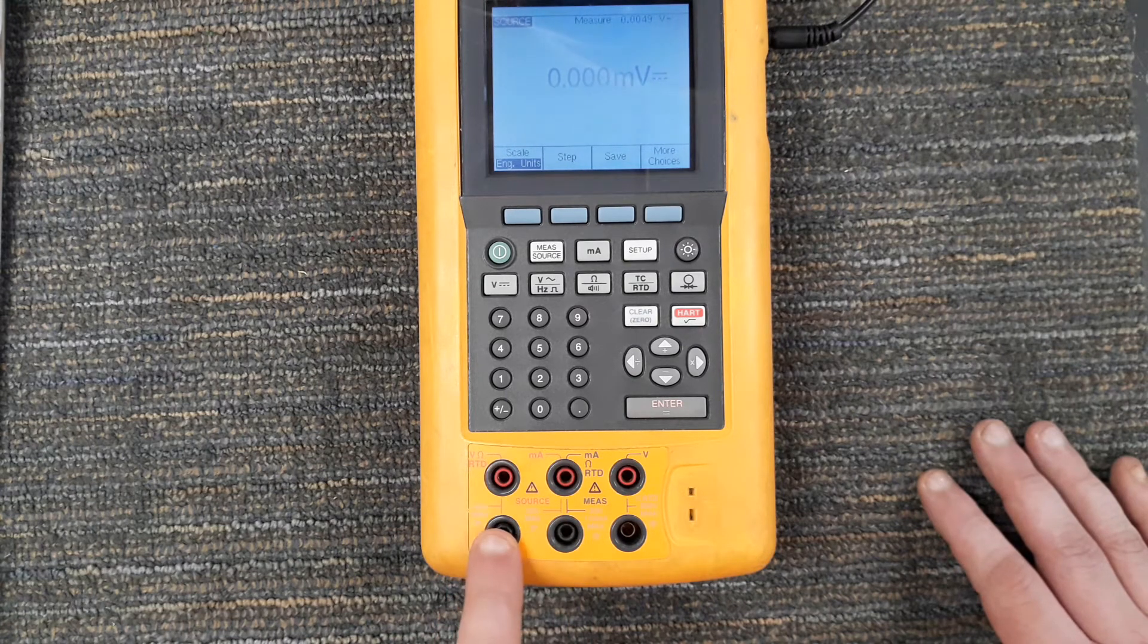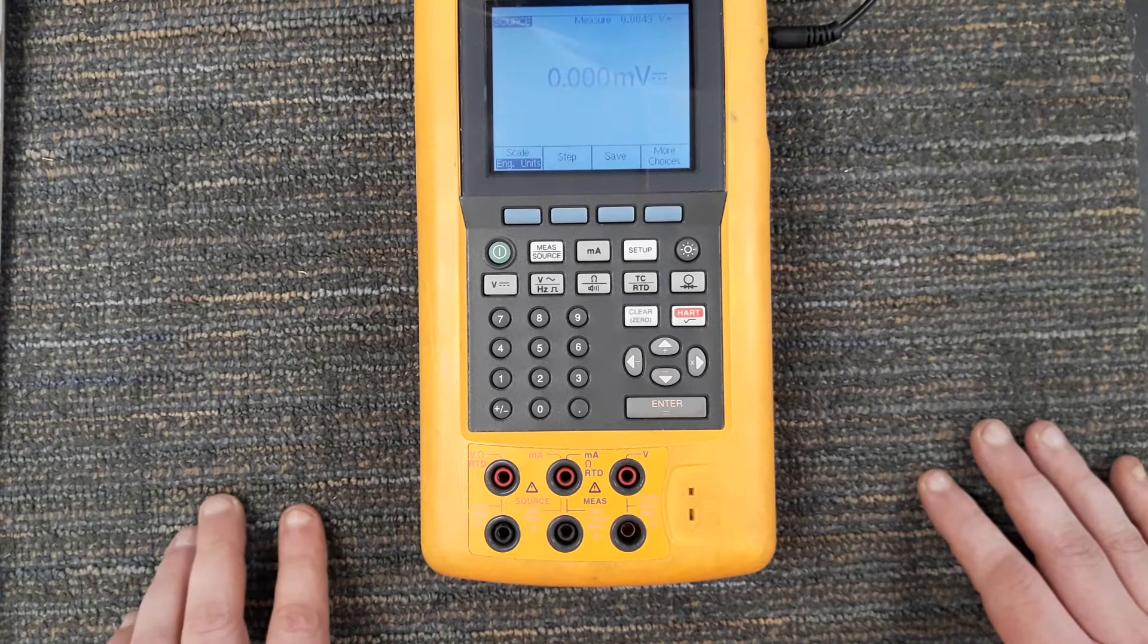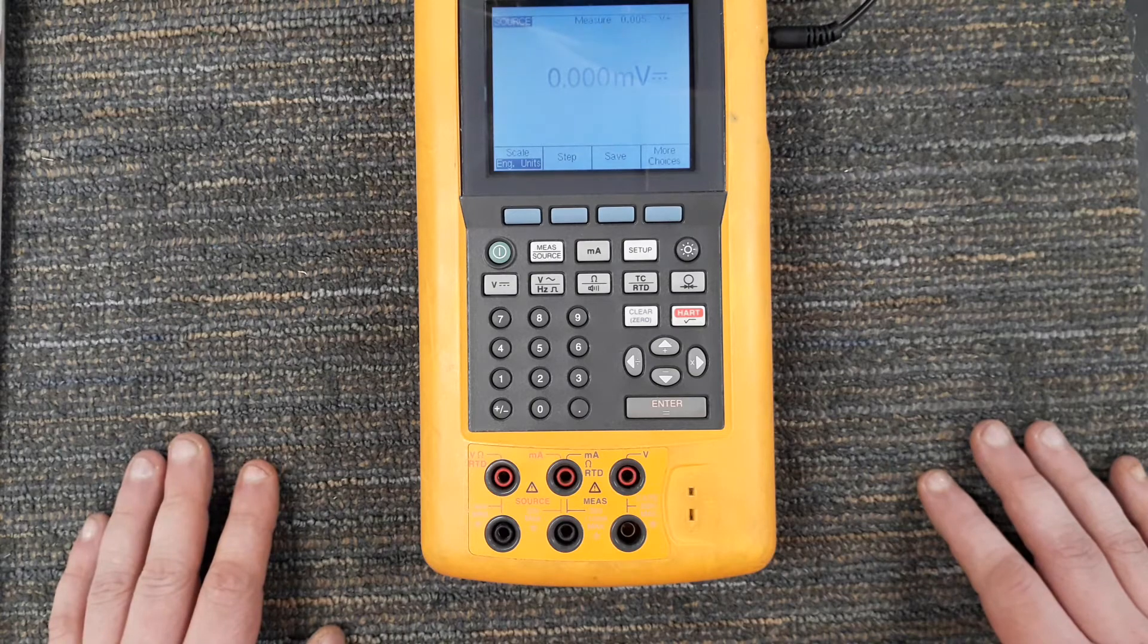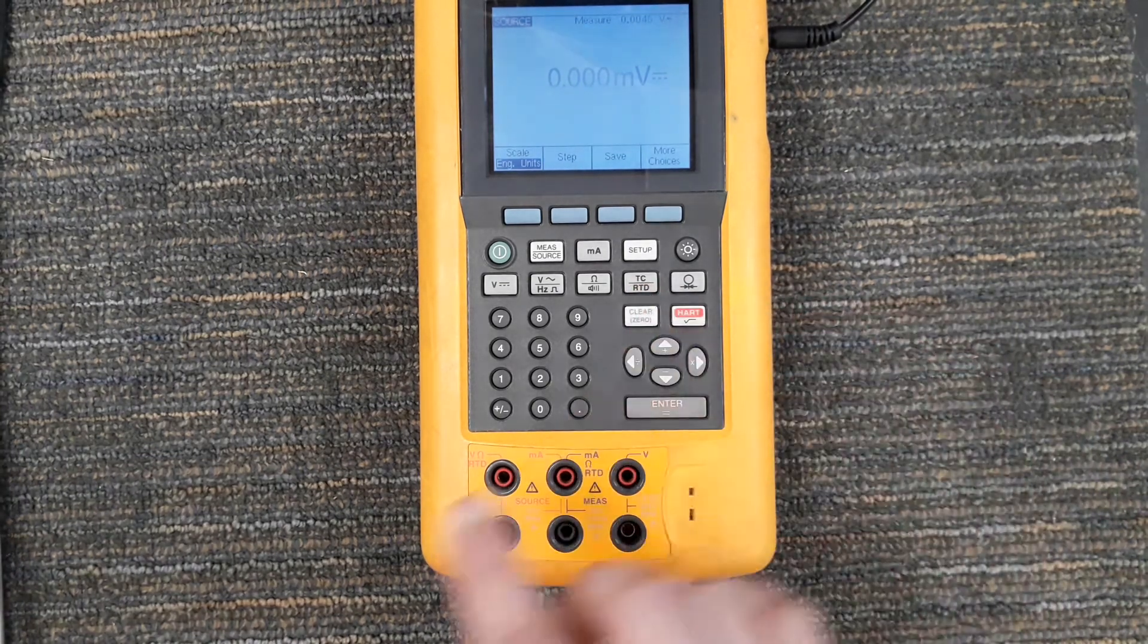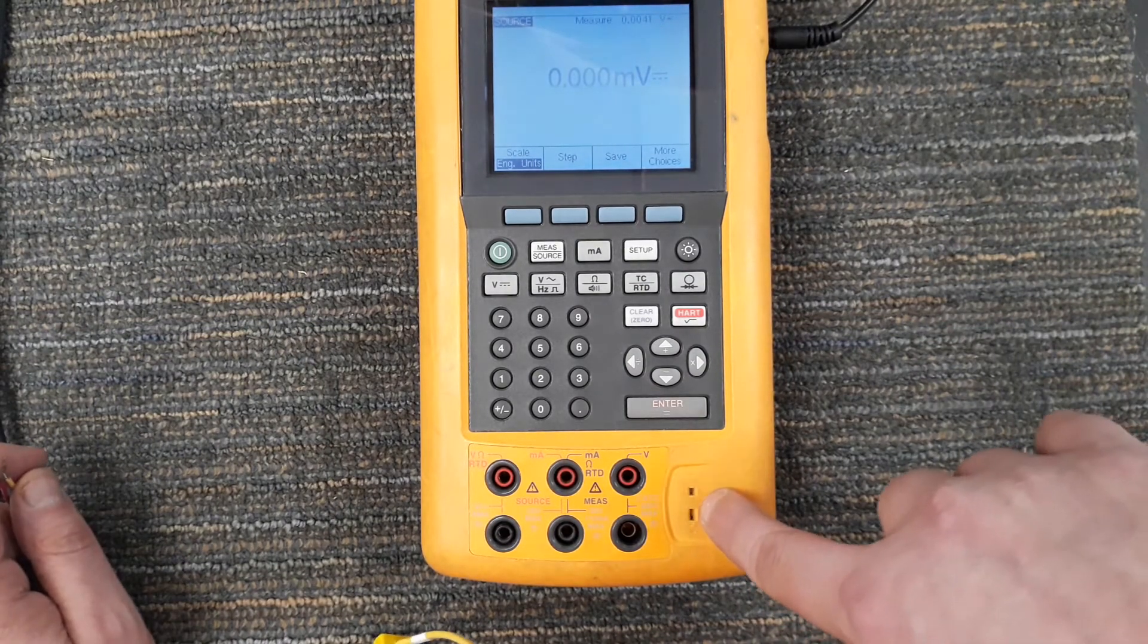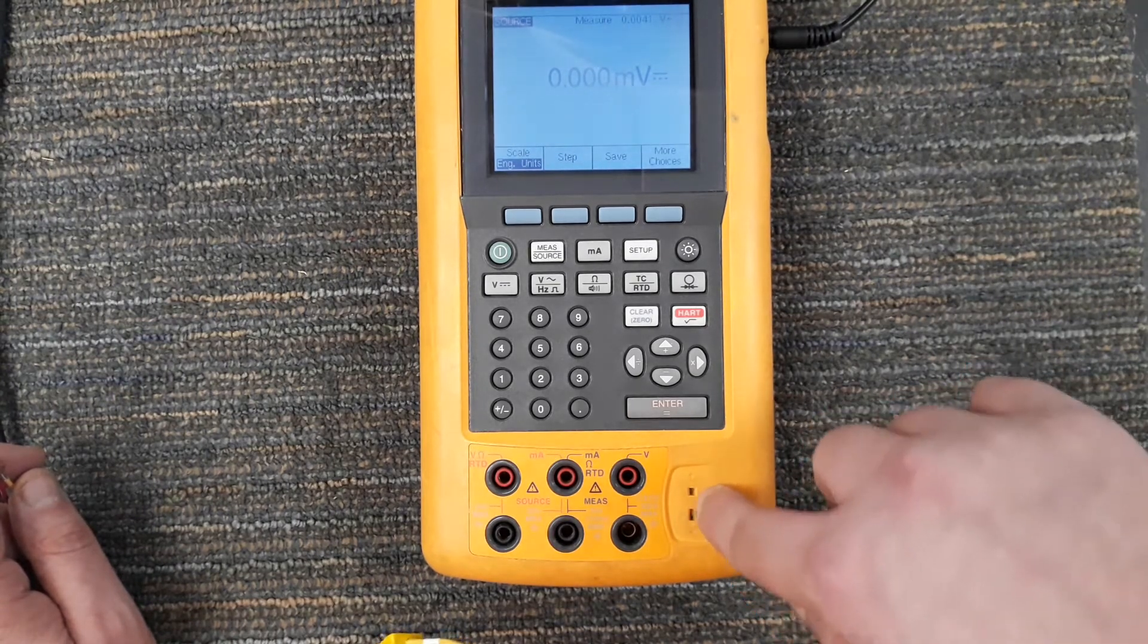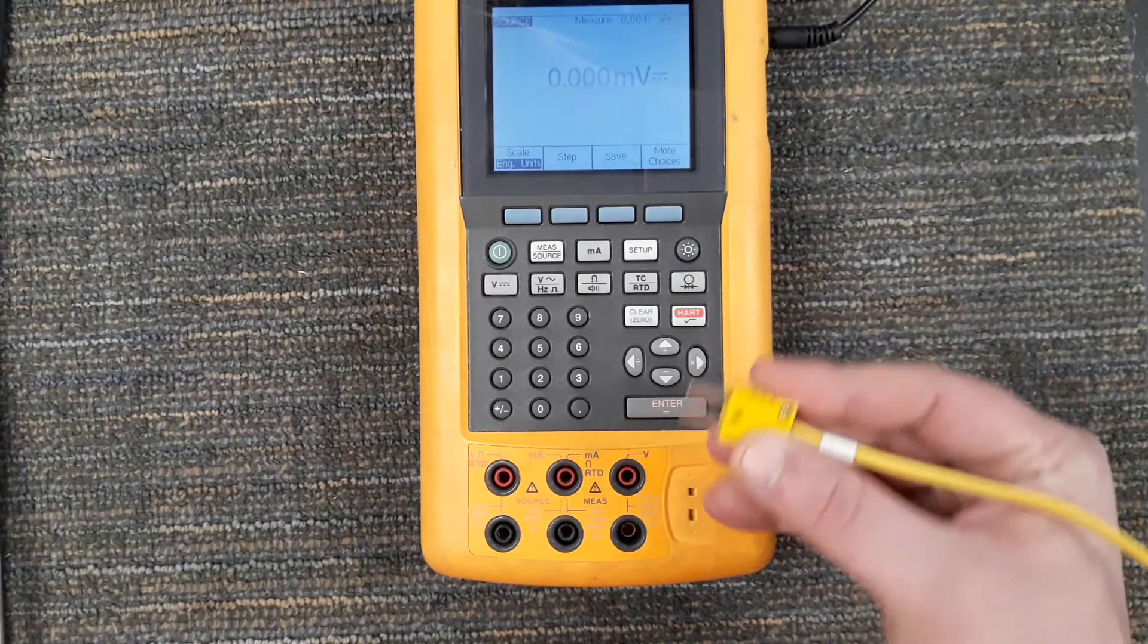Now if I wanted to source resistance I'd have to go over here - sources red. I'm going to source resistance or RTDs. Sourcing voltage is over here, and then sourcing current is here. And then you also see as we talked about the thermocouple and the RTD, this port here or this, what we could call a thermocouple port, this is where we're going to plug in a thermocouple extension which you're going to be getting familiar with in our labs.